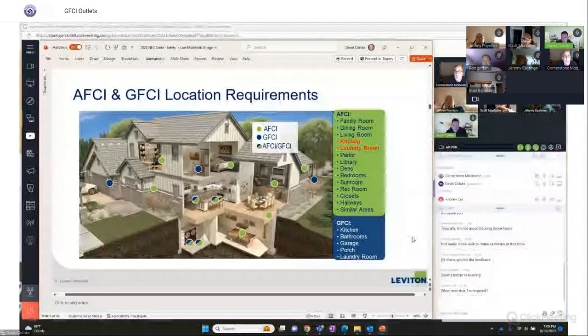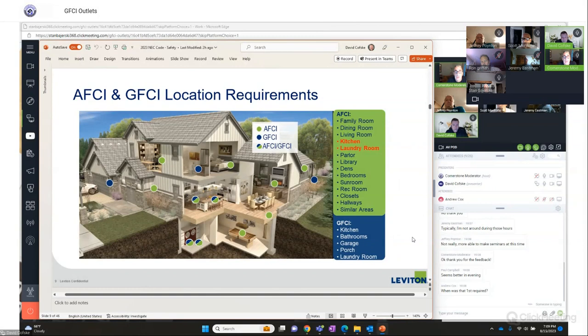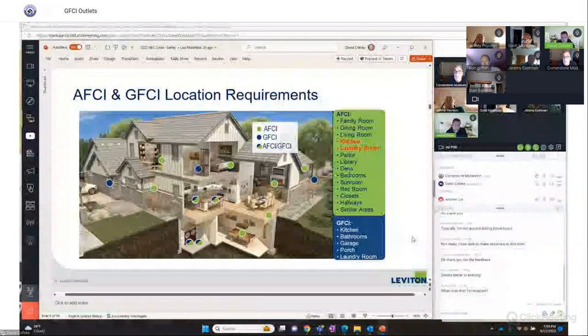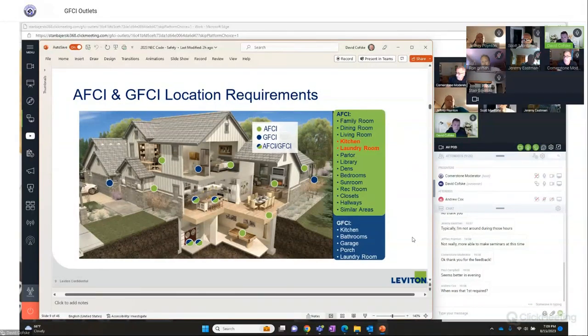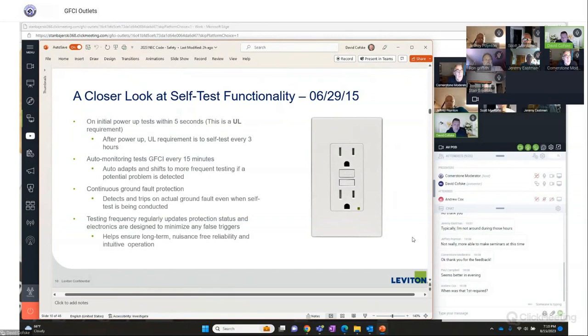David, so when were these first required? Do you know the year? So GFCIs were probably the first, and they probably go back to maybe the early 80s, I'm guessing. Okay. So they've been around for a long time, the GFCIs. I think I've got a slide coming. Let's see if it's coming up next. GFCIs, for the most part, were a test and reset type of device. So when you used to buy and install them, they came with some instructions. And I guess we know how people like reading instructions or taking direction. We don't do it very well. Those devices never got tested. The only time it ever got tested was when it tripped. Someone would reset it, and if it would hold, life went on.